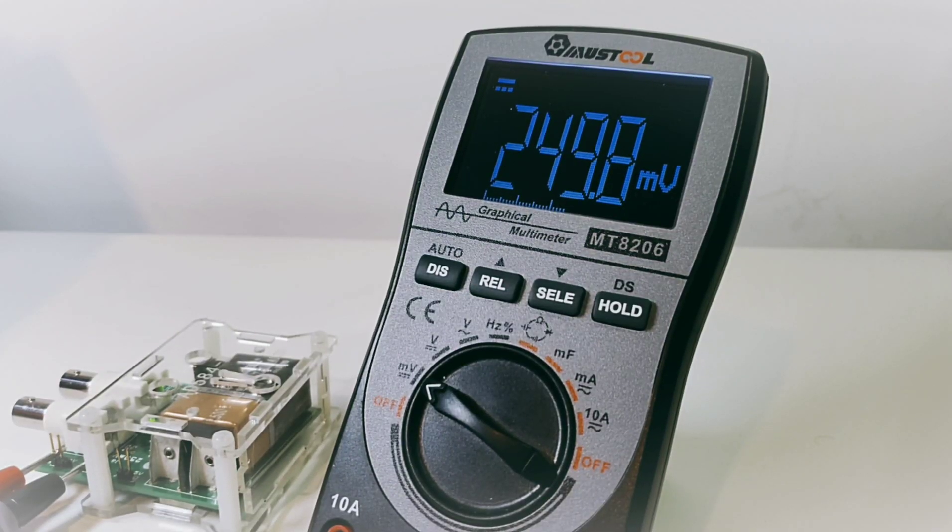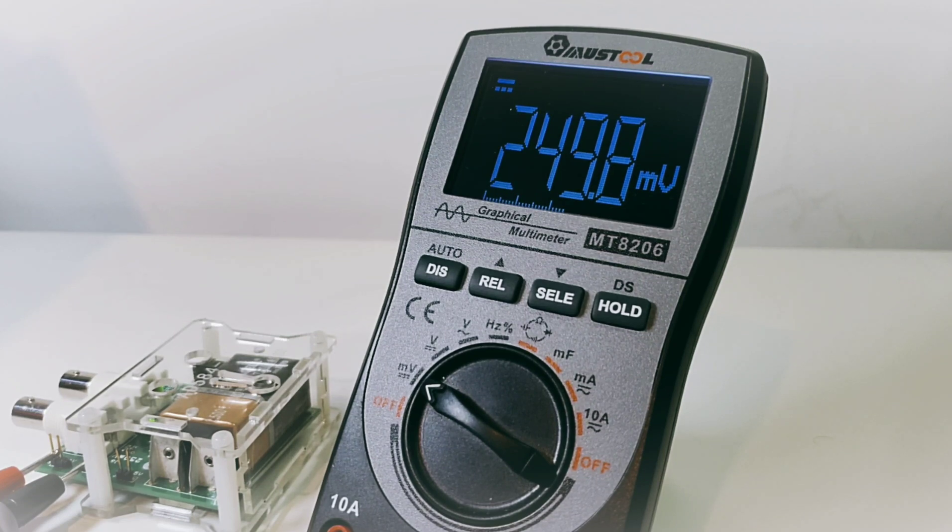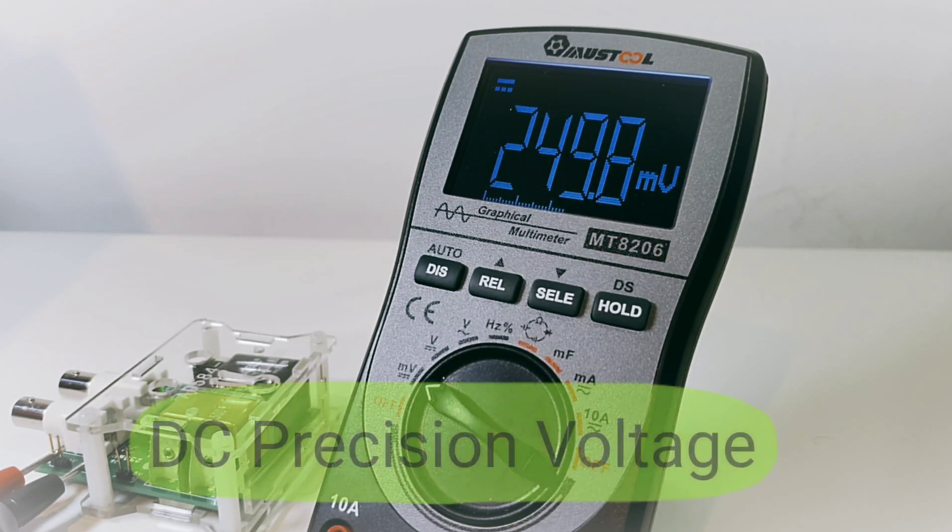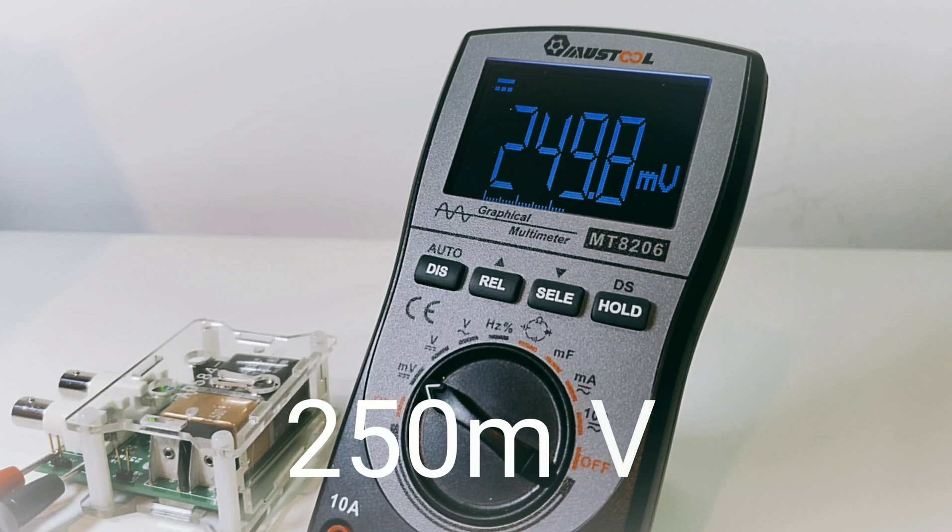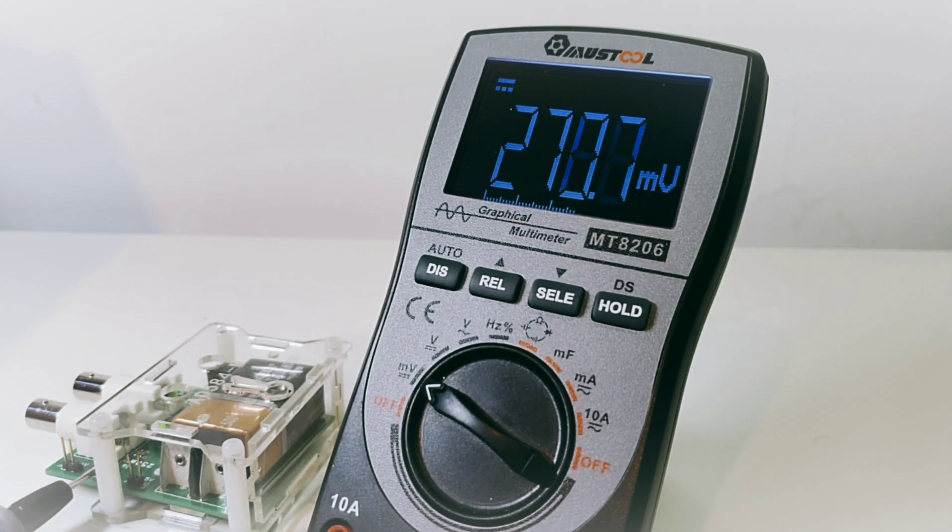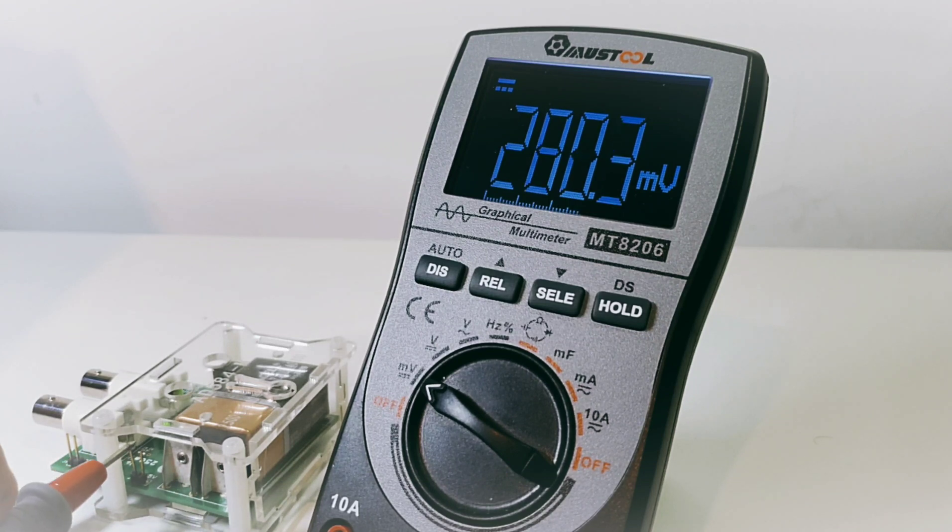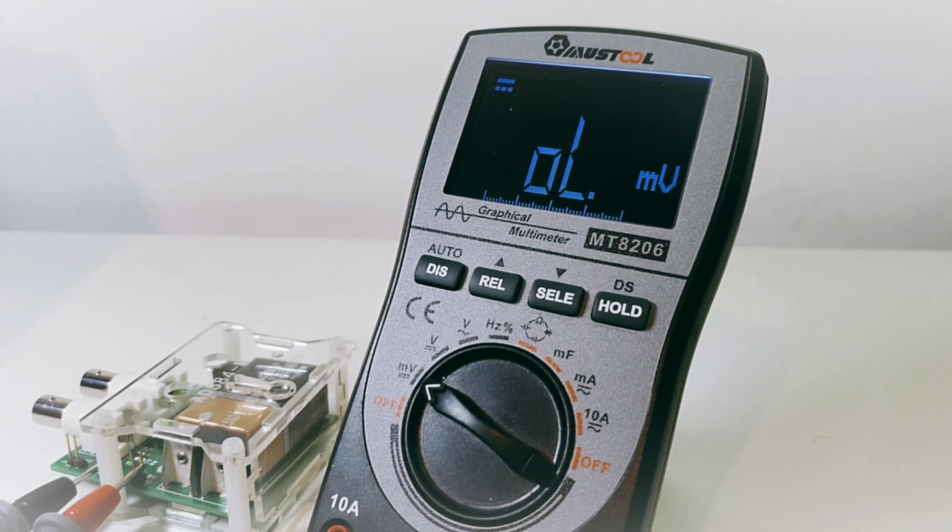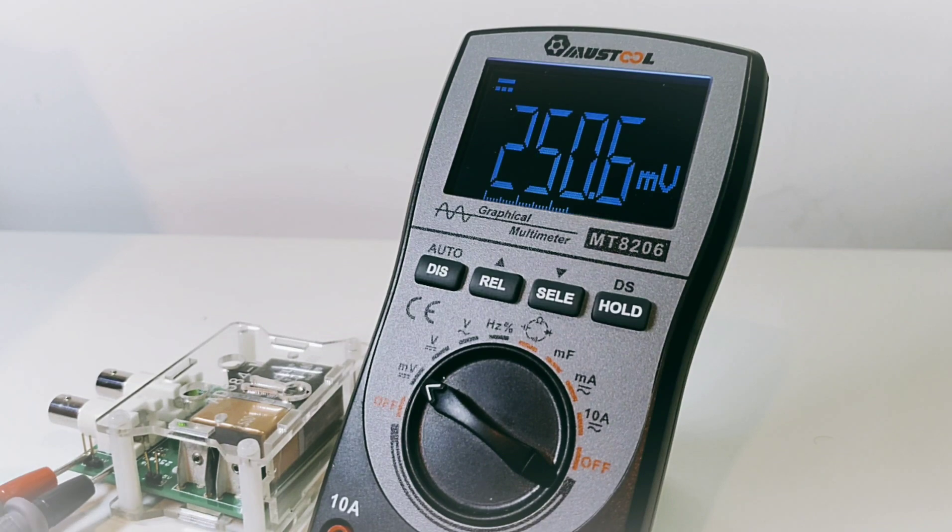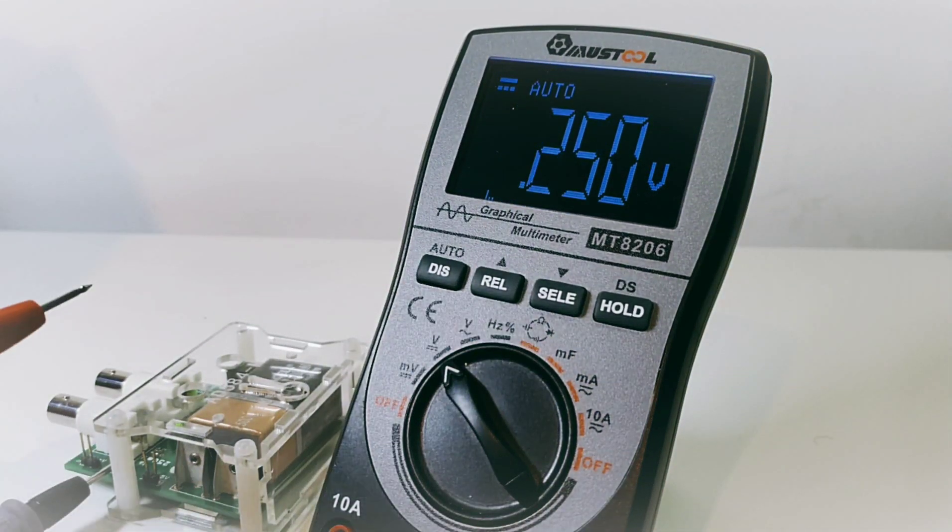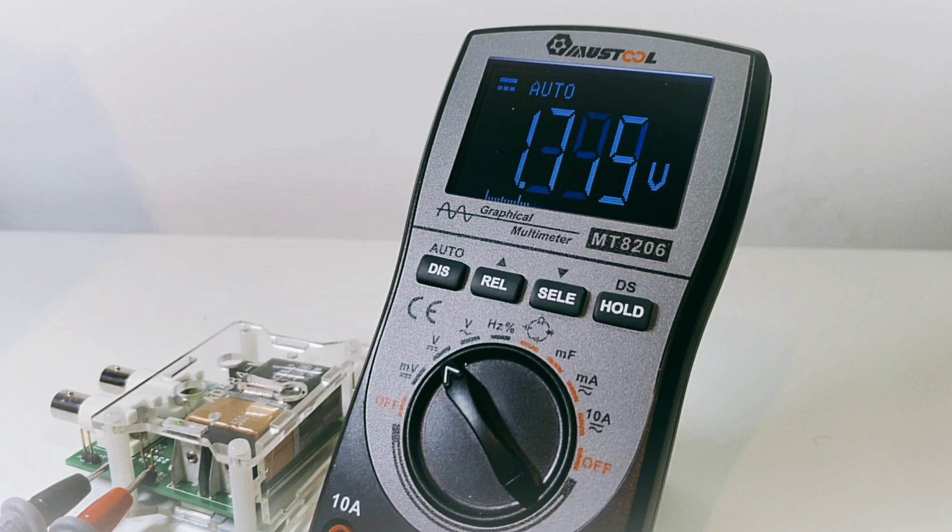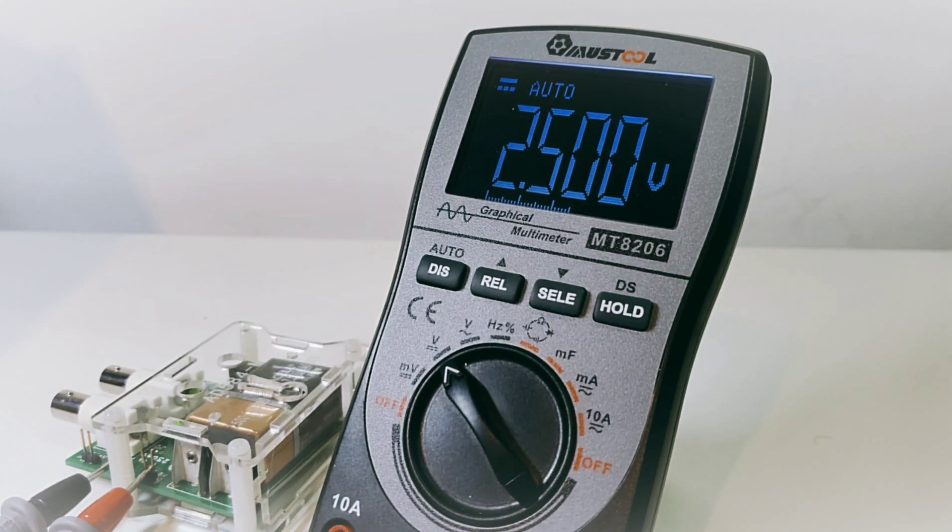Starting things off, we have the voltage reference out sitting at 250 millivolts. We are in millivolt mode and you can see it is kind of going back and forth. I'm going to give it 250 just because this reference has not been heating up for very long. I've taken out the probe, we're still in millivolt mode and it's telling us that we are over-range. So I'm going to switch it to volts DC. We should be looking at 2.50 volts. Spot on.